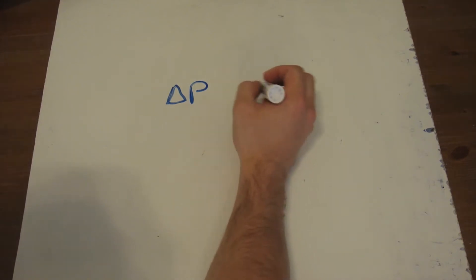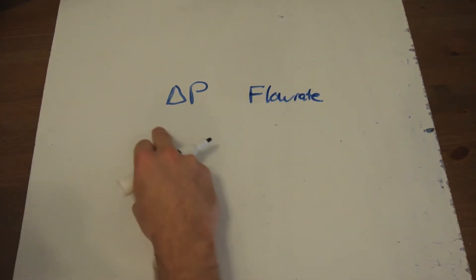Well if we remember back to Bernoulli, we can say that there's going to be a relationship between the delta P and the flow rate of the fluid in the pipe and the relationship between those two is going to be a square root relationship.